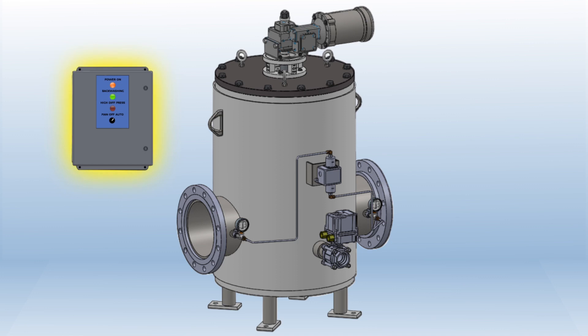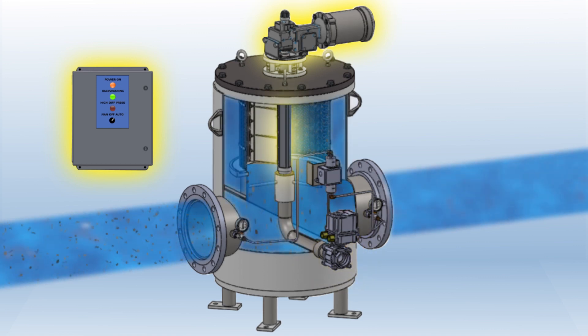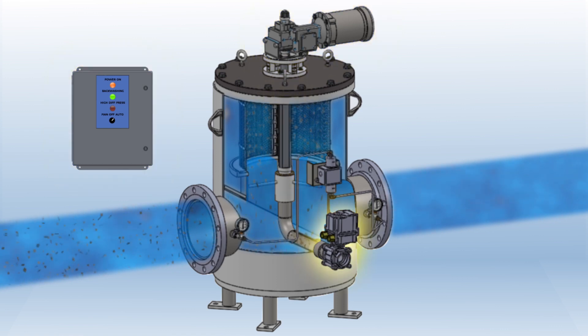The control panel energizes the electric motor and backwash control valve. The electric motor causes the cleaning shaft to rotate and the backwash cleaning port moves slowly around the inside of the screen.